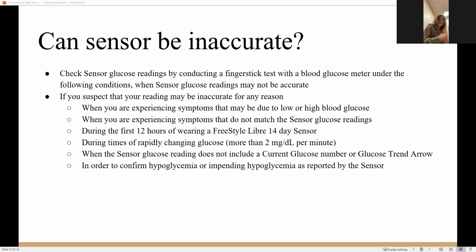Other reasons that the CGM can be inaccurate is due to rapid fluctuations in blood sugars. So it just can get off for periods of time. Even though it might be off today by 20 or 30 points, that's actually considered an average or an okay number, but patients will say, well, it's dead on, it's never been 20 or 30 points off. And usually that's because they haven't experienced any rapidly changing blood sugar readings. So if they do more than 2 milligrams per minute, many times the CGM will actually become off.